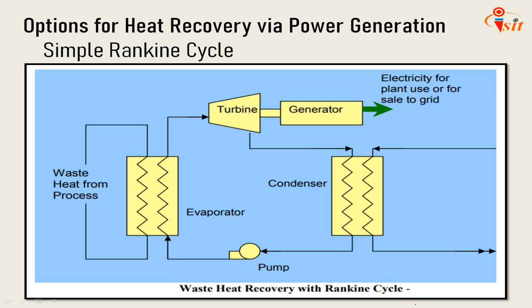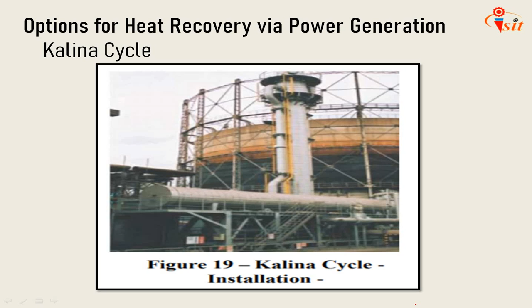Next one is the Kalina cycle. The Kalina cycle is a variation of the Rankine cycle using a mixture of ammonia and water as the working fluid. A key difference between single fluid cycles and cycles that use binary fluids is the temperature profile during boiling and condensation. For single fluid cycles, the temperature remains constant during boiling. As heat is transferred to a working medium, the water temperature slowly increases to boiling temperature, at which point the temperature remains constant until all the water has evaporated. A binary mixture of water and ammonia will increase its temperature during evaporation. This allows better thermal matching with the waste heat source and with the cooling medium in the condenser. Consequently, these systems achieve significantly greater energy efficiency.